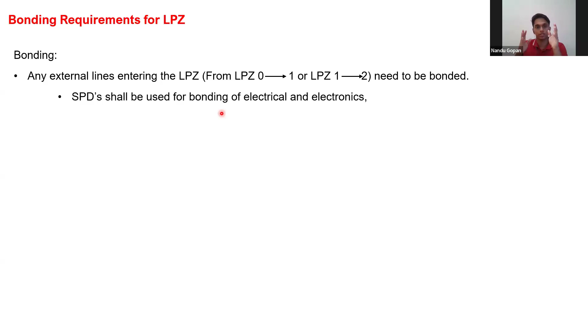The reason you are supposed to bond it is so that surge currents spread across the installation, and the potential remains the same across the installation. That is the major point of bonding - if you touch any pipelines and good bonding has been done, you will not get a shock, because wherever you are standing or touching with your other hand will be at the same potential.